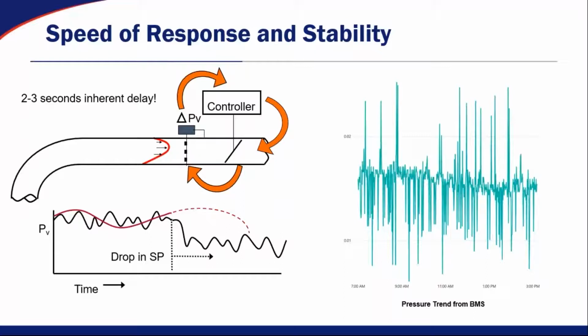So if you slow down the control loop, you get more deliberate control, you get less hunting, but that also means when you have system changes, it's going to take a lot longer for your building to react. I've actually talked to some people that say they give about 30 to 45 minutes for their system to be able to change pressure when they go from occupied to unoccupied.